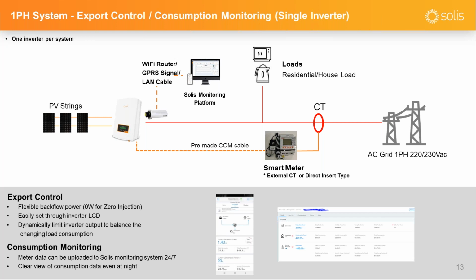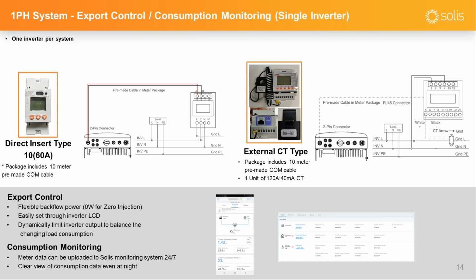Okay, so previously we talked about one inverter per system, and now there is the meter, where we talk about the direct insert type and also the external CT type, together with detailed diagrams of how to connect the meter. For the details, you can refer to the user manual of the inverter. For the direct insert type meter, the package also includes a 10 meter pre-made COM cable for the communication between the inverter and the meter. The external CT type also comes with the 10 meter pre-made COM cable, and another unit, the CT, which is a 120 amp CT for the current sampling.